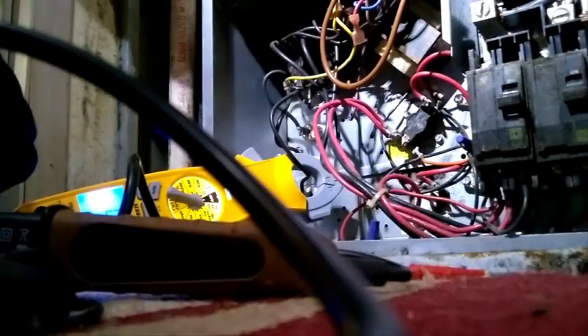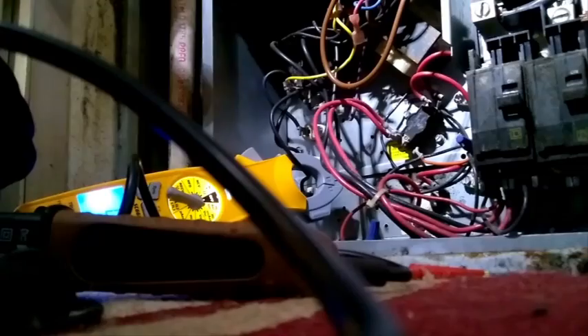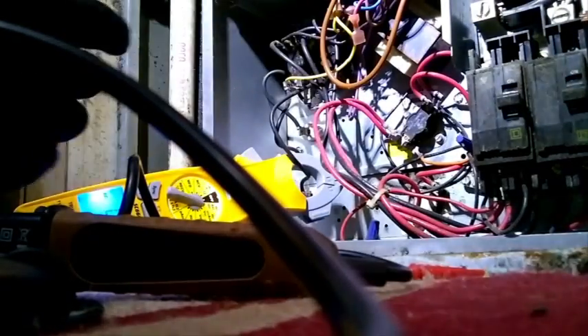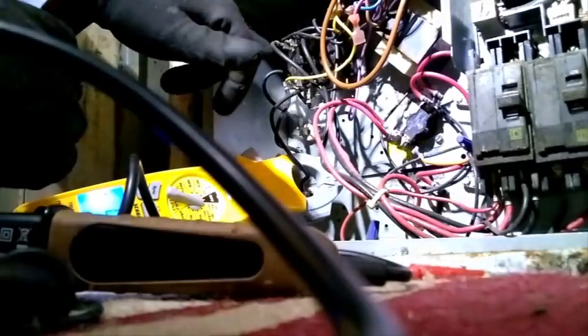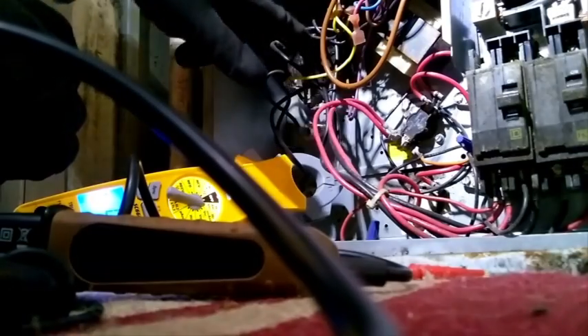One of them's not coming on every time, that's why your blower's not coming on. The other one does come on, so it actually runs without the blower, overheats, and shuts down. That's why you don't get any heating when that happens. Sometimes this one is clicking on, and it's causing issues because that one turns the blower on. It's supposed to come on first, turn the blower on with the first set of elements, then the second one comes on. But the only one coming on right now is the second one.